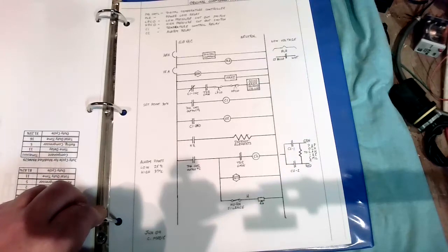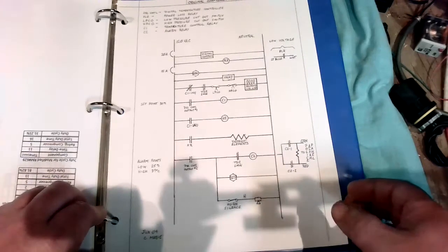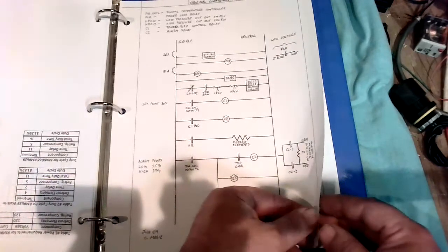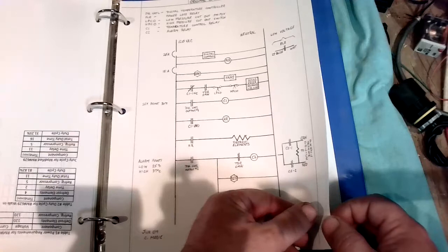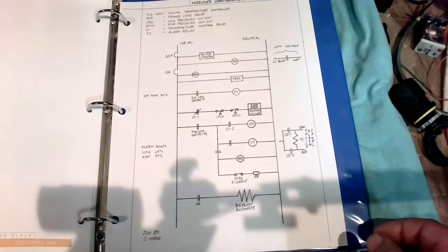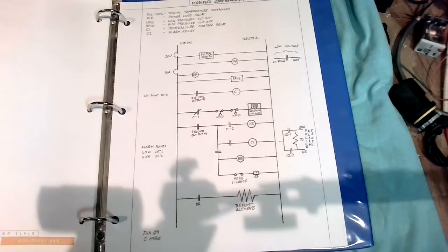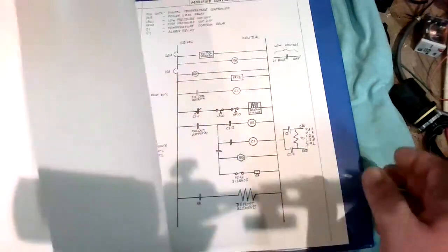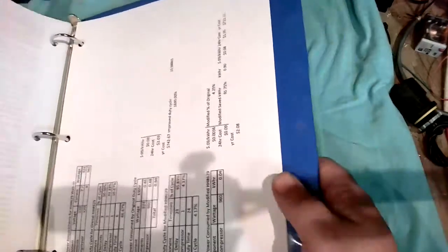So I looked at it and go, hey, if we change up the relay logic a bit, we can improve the duty cycle, and it would stop short cycling the system. So I ended up rewiring it with approval, of course. I didn't just do this willy-nilly. So I rewired it and was able to show, yes, an improvement. Here's my little write-up for it and everything else. So that was boring stuff.